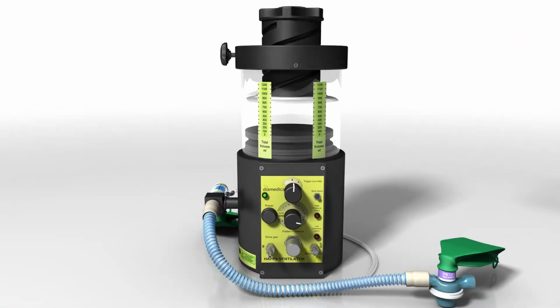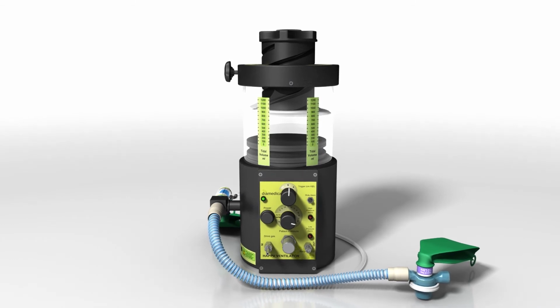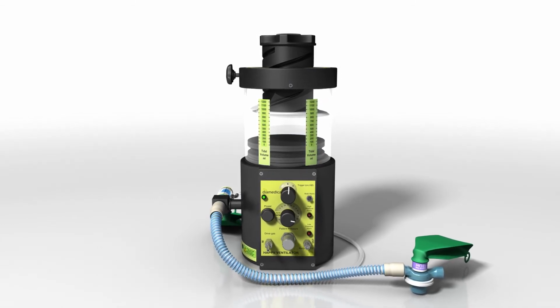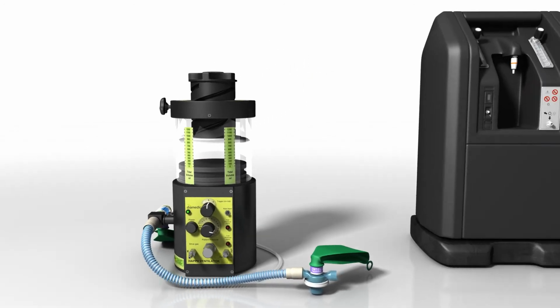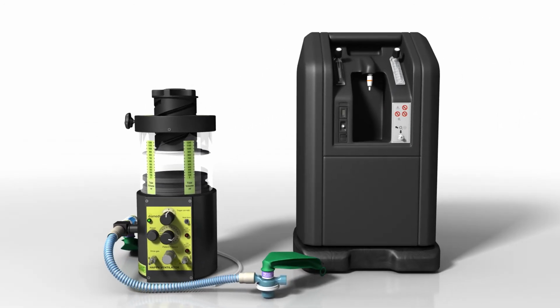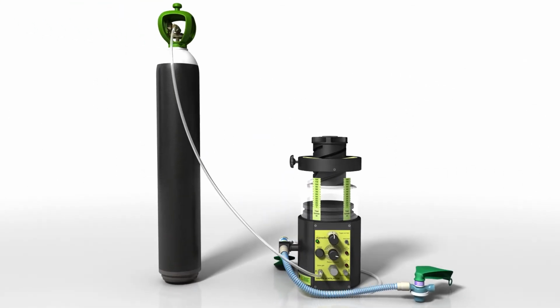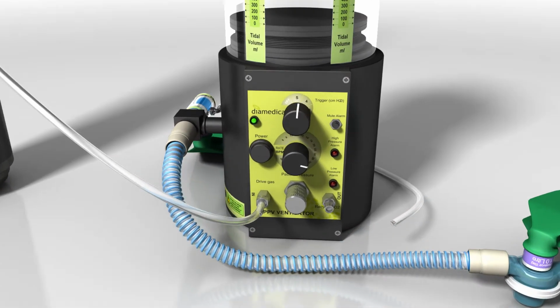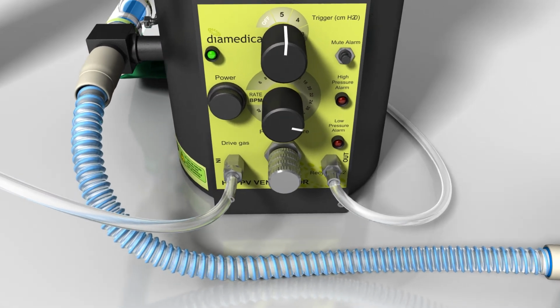The ventilator can be driven by any gas supply from 1.5 bar, 20 psi, to 5 bar, 75 psi. If a suitable oxygen concentrator is used, the drive gas tube can simply be connected directly from the concentrator outlet to the drive gas inlet on the ventilator. If the gas source is from an oxygen cylinder, the drive gas tube is connected to the cylinder 4-bar regulator. If oxygen is the drive gas, it can be recycled into the patient circuit to increase the FiO2 through this tube from the drive gas outlet to the circuit block.